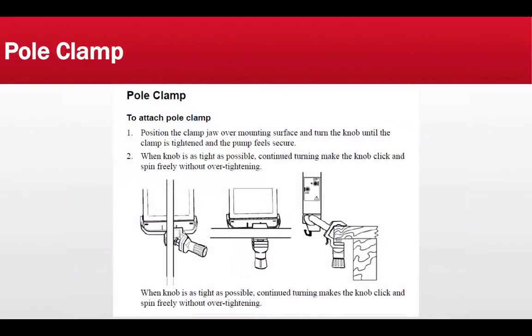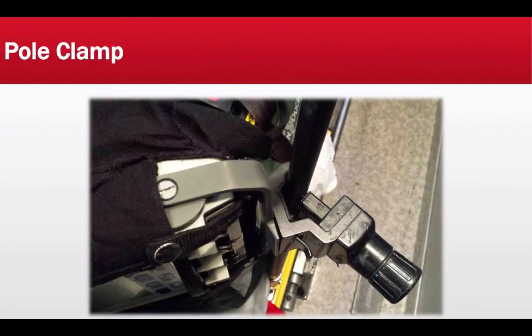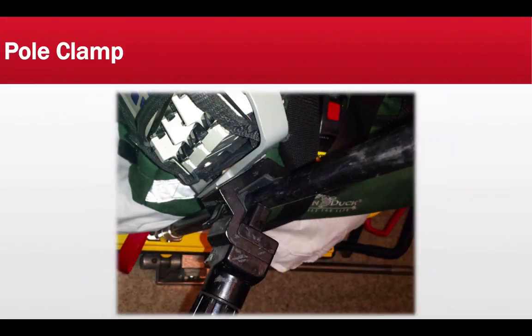Pole clamp. So the pole clamp can be mounted to any device, either a pole, a shortboard, or another device that you may employ. The trick here is once you locate your surface, keep turning the knob until the clamp is tight and the pump feels very secure, and then continue turning to make sure the knob clicks and spins freely without over tightening it. So I'll have the close-up pictures here. This is the IV pump mounted to a pole on the stretcher. So keep turning it until it clicks and it spins freely and you cannot turn it anymore. This is just another picture showing you the same connection.